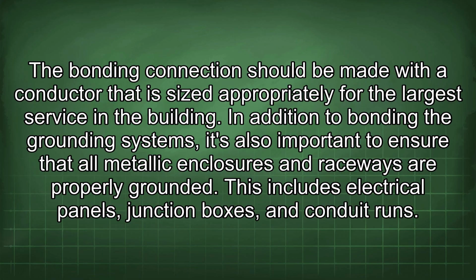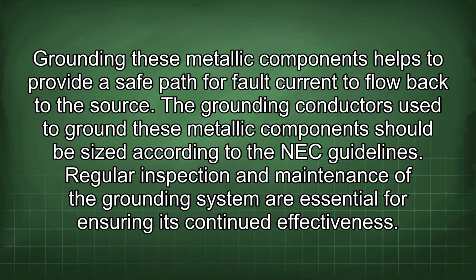In addition to bonding the grounding systems, it's also important to ensure that all metallic enclosures and raceways are properly grounded. This includes electrical panels, junction boxes, and conduit runs. Grounding these metallic components helps to provide a safe path for fault current to flow back to the source. The grounding conductors used to ground these metallic components should be sized according to the NEC guidelines.